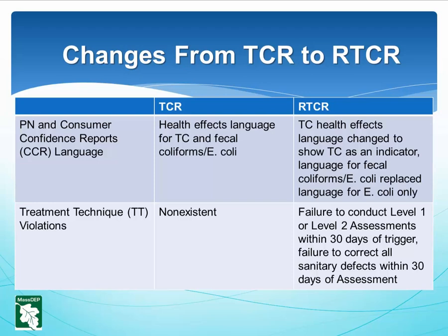In the TCR, there were no Treatment Technique violations. In the RTCR, since there are now Level 1 and Level 2 assessments, there are Treatment Technique Violations for failure to conduct Level 1 or Level 2 assessments within 30 days of an assessment trigger, and failure to correct all sanitary defects within 30 days of the assessment after you are made aware of the defect.